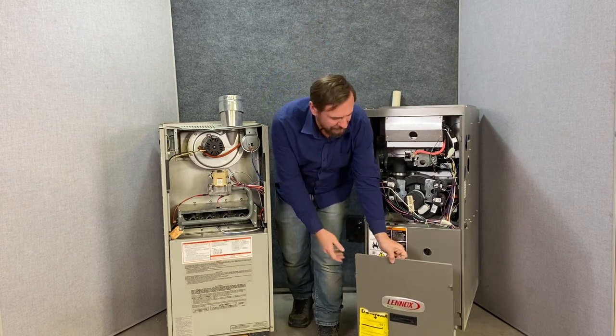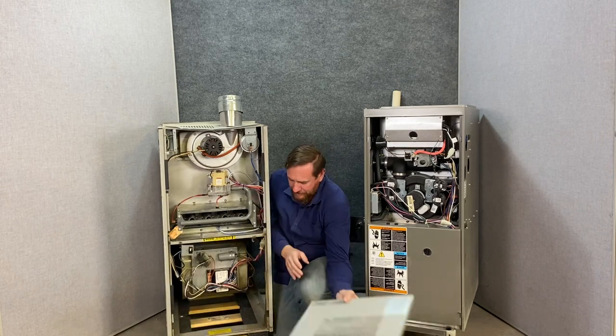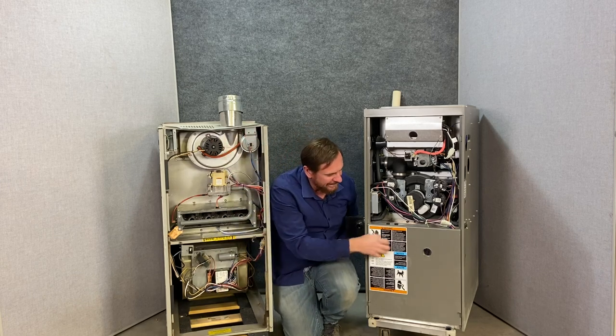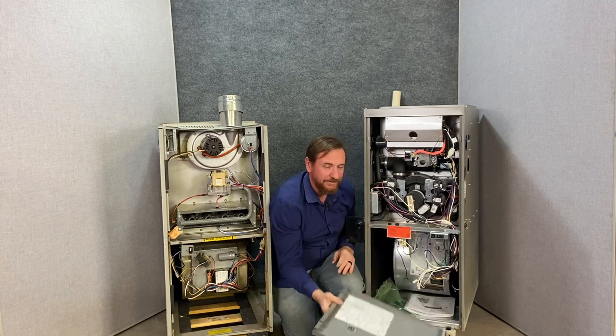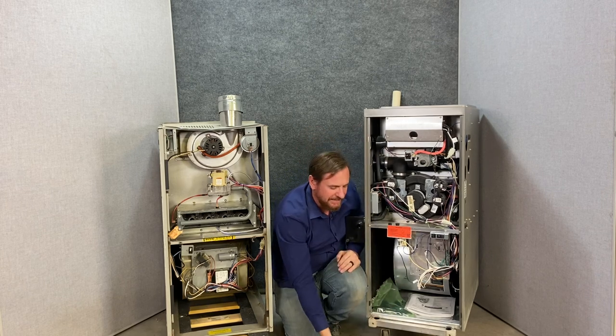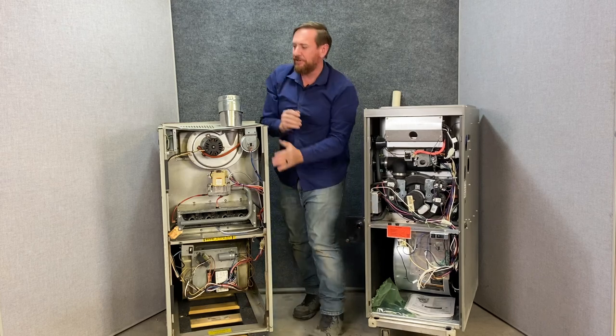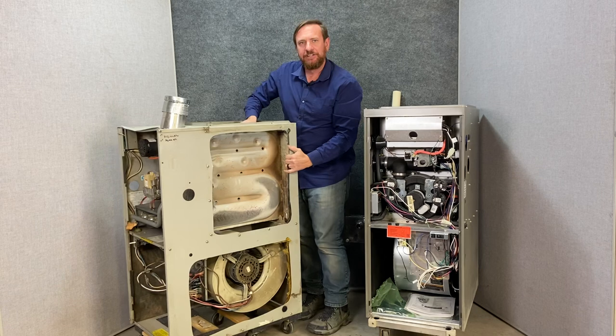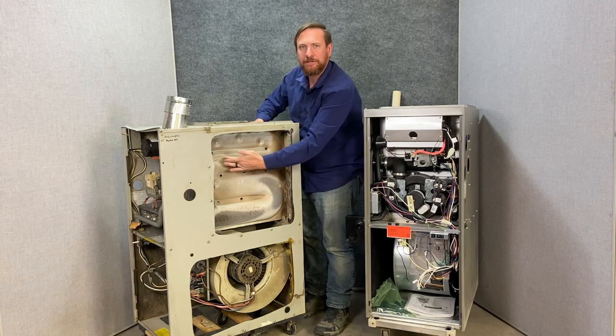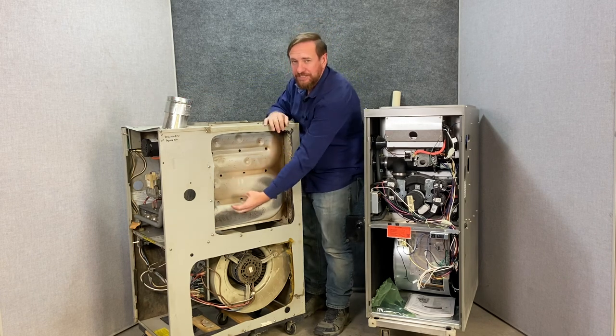On the bottom door of both furnaces is where we have our IFCs and blower motors. The blower motor pushes air through the heat exchanger and into the house. There are some very big differences I want to point out in these heat exchangers. The 80% furnace has burners at the bottom — the flame burns up to a certain point, then it's just hot gases going back and forth, with the inducer fan motor pulling or inducing that flame to burn sideways.